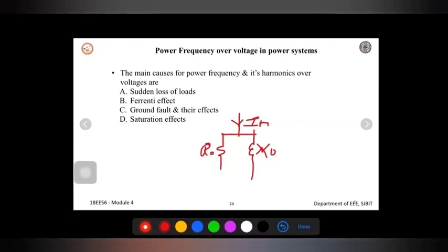This magnetizing current, which is the no load current, will increase rapidly whenever you give a voltage above the rated voltage for any power transformer. It may increase to about full rated current at 50% over voltage.